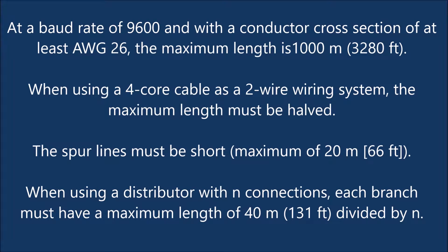At a baud rate of 9,600 and with a conductor cross-section of at least AWG-26, the maximum length is 1,000 meters (3,280 feet). When using a four-core cable as a two-wire wiring system, the maximum length must be halved.